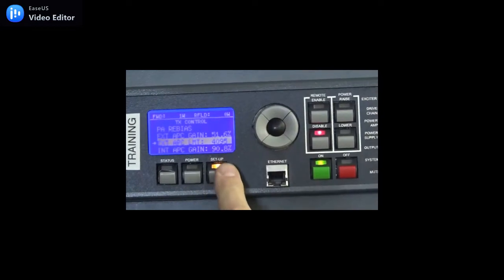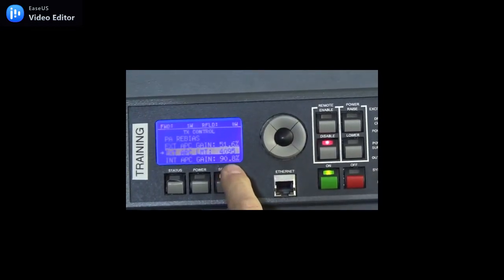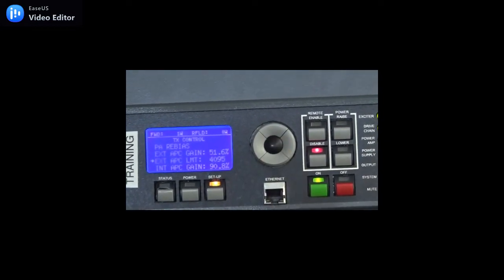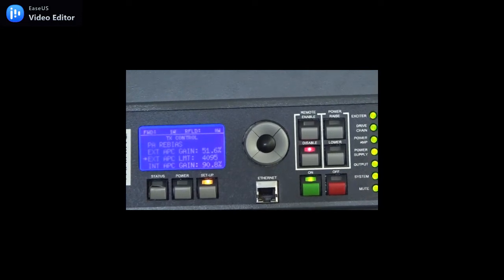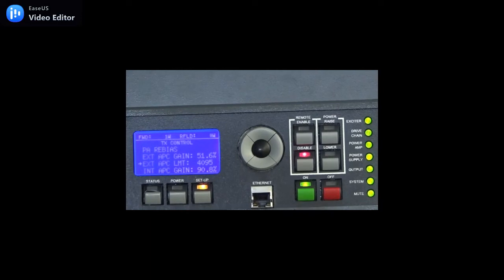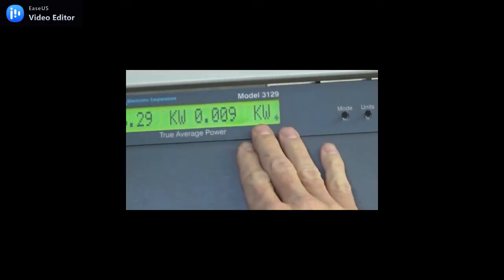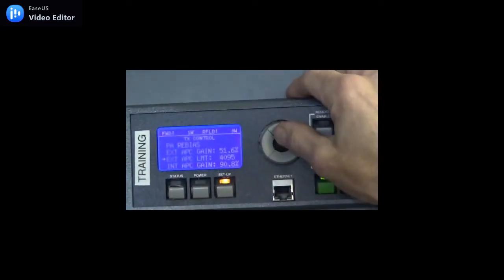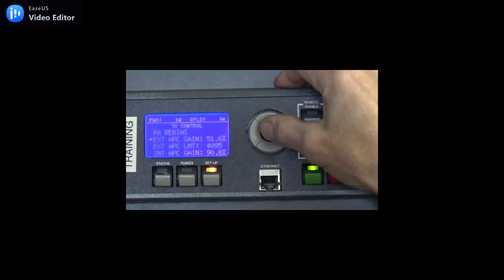Okay, so the maximum number there is 4,095. Press that. What that allows us to do is to raise the external APC gain and not limit us. So if you don't raise that up off the limit, you may not be able to get all the way up to your TPO. So now we're there. So the next step is to raise the transmitter power.